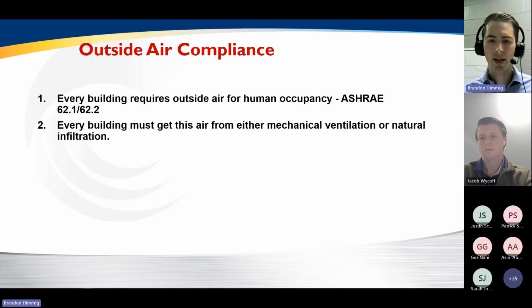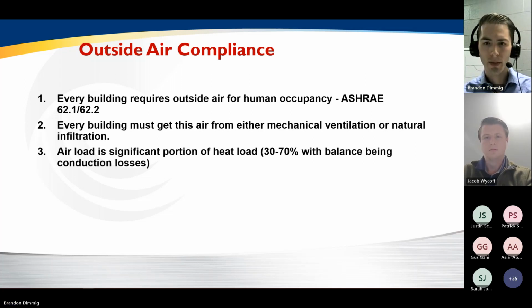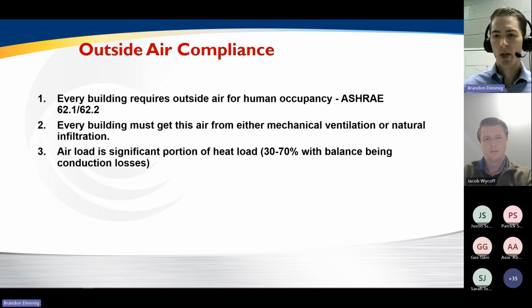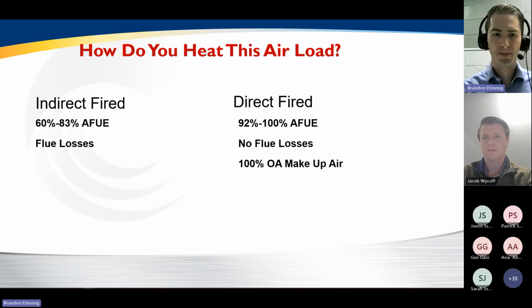Mechanical ventilation, on the other hand, allows for consistently ventilated buildings. You can bring it in at prescribed locations, and you can really control the building environment much better. But the reality is that this puts an air load on the building, air that must be heated, especially when it gets cold outside. So if it's 0 degrees outside, that air has got to be heated up somehow. In many cases, it can be a significant portion of the overall building's heat load, with the remaining part being conduction losses. So we're going to look at how you heat the air load, how you heat the conduction load, and what HTHV's role is in that.